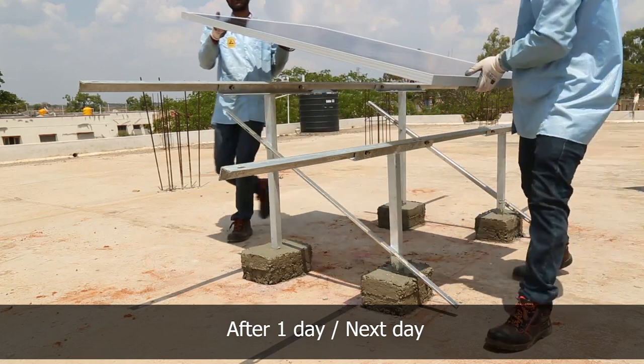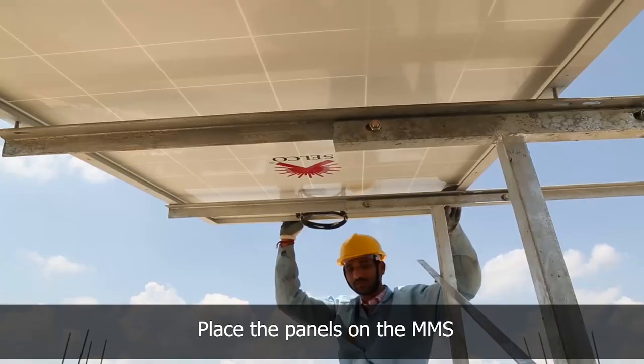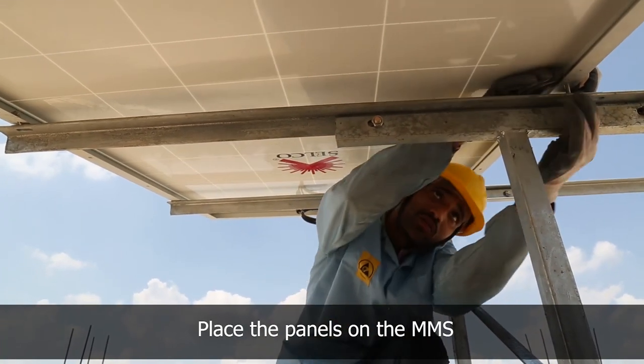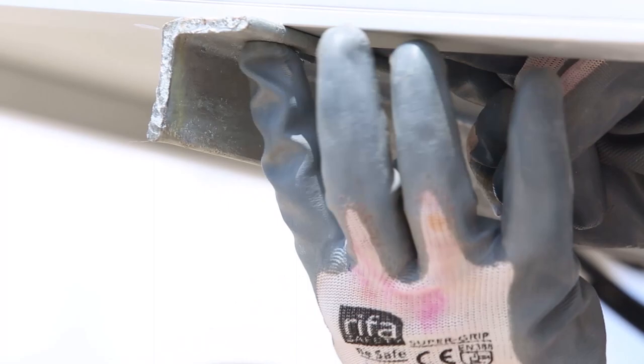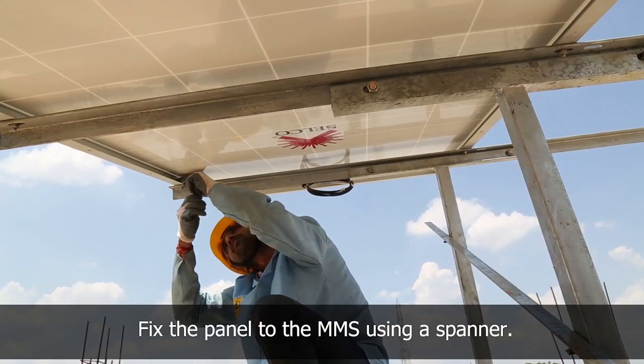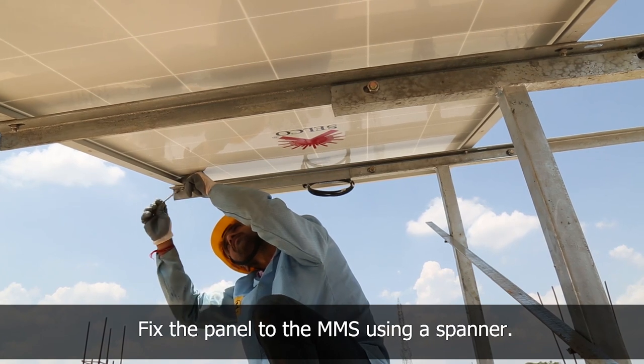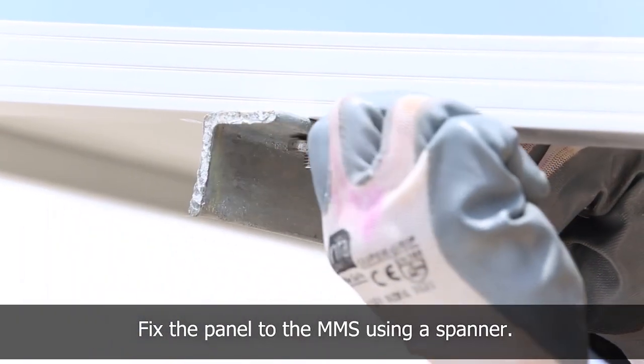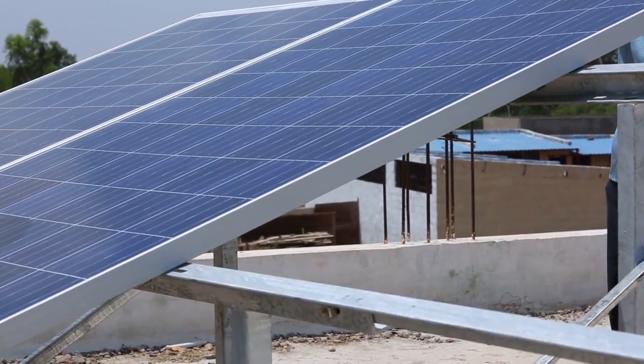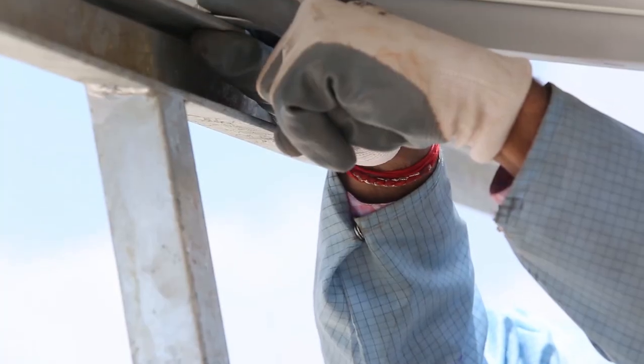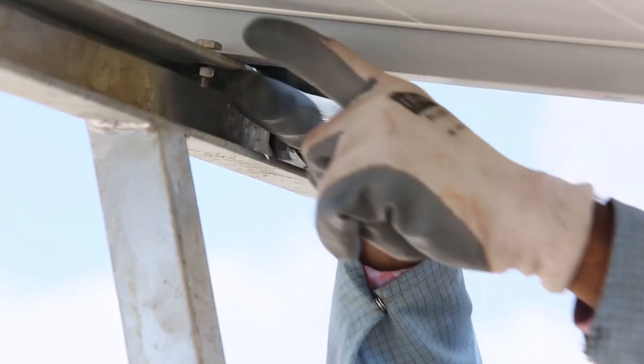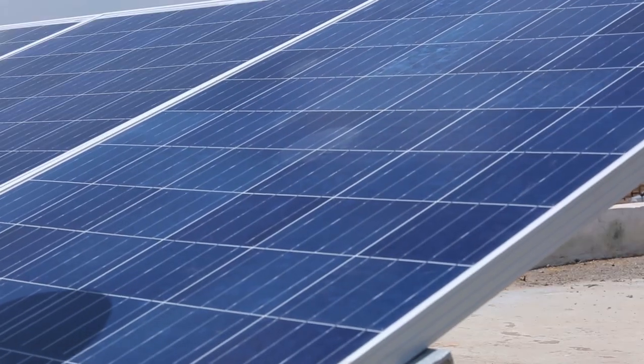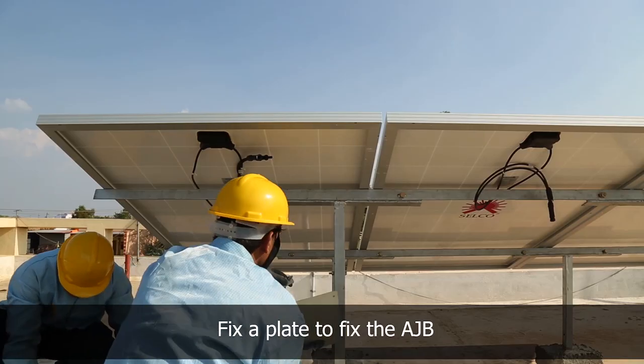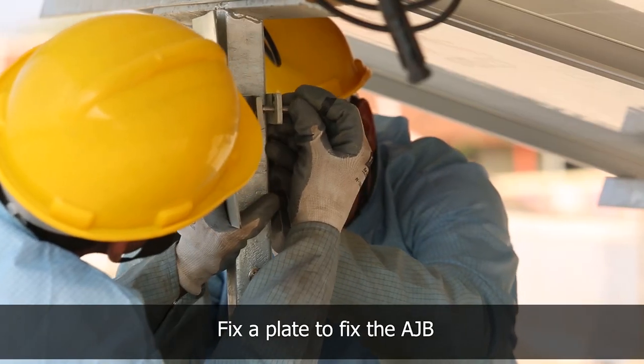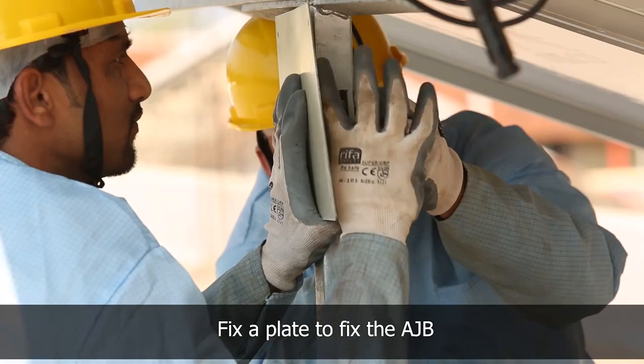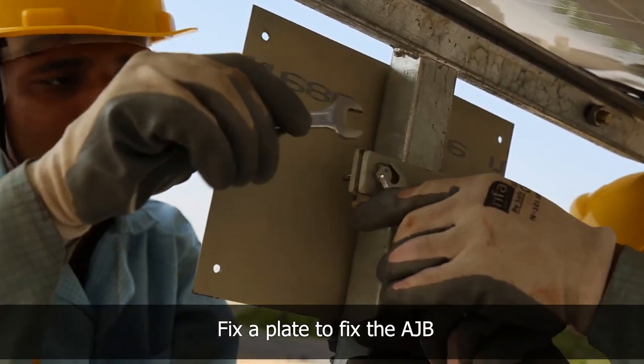After one day, place the panels on the module mounting structure. Fix the panels to the module mounting structure using nuts and bolts, and tighten using spanners. Fix a plate to fix the array junction box to one of the legs of the module mounting structure using nuts and bolts, and tighten using two spanners.